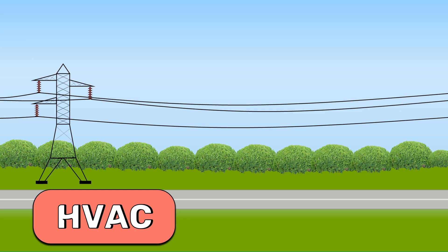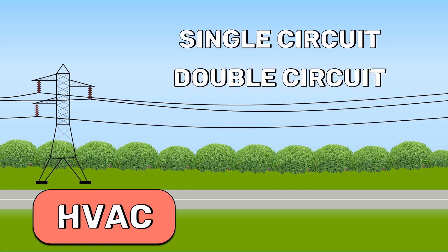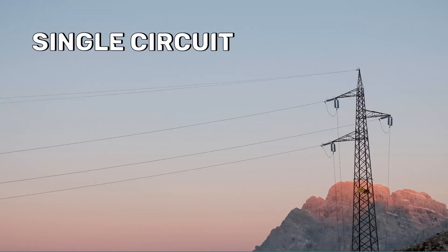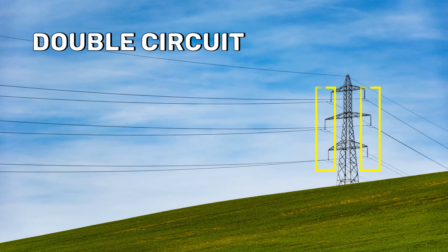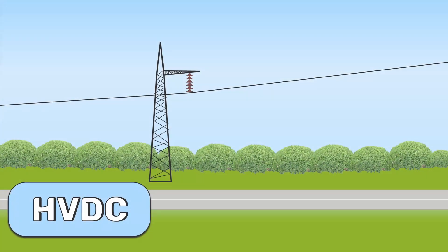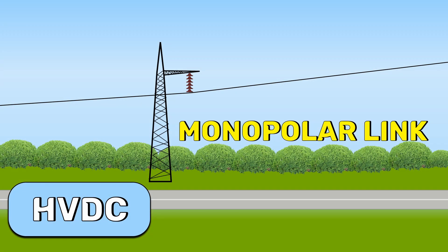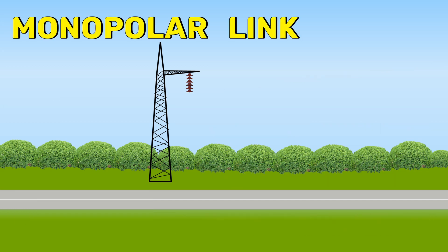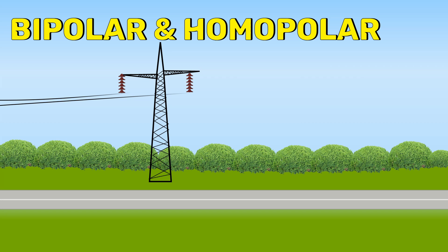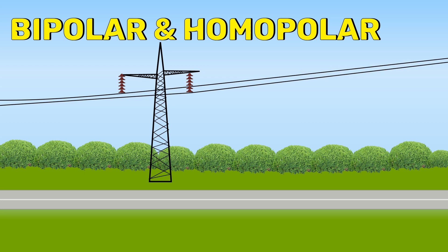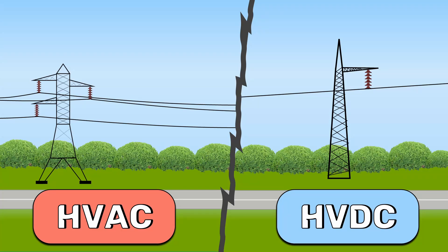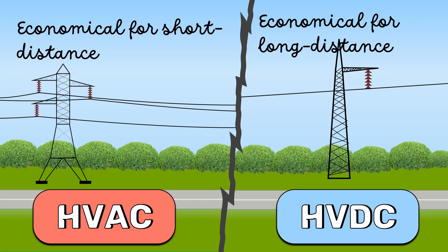In HVAC, we have single circuit transmission lines and double circuit transmission lines. A single circuit transmission line has three sets of conductors, while a double circuit transmission line has two independent circuits, meaning it has six conductors. The three types of HVDC links are monopolar link, bipolar link, and homopolar link. The monopolar link has only one conductor, while bipolar and homopolar links have two conductors. HVAC transmission is economical only for short-distance transmission, while HVDC is economical for long-distance transmission.